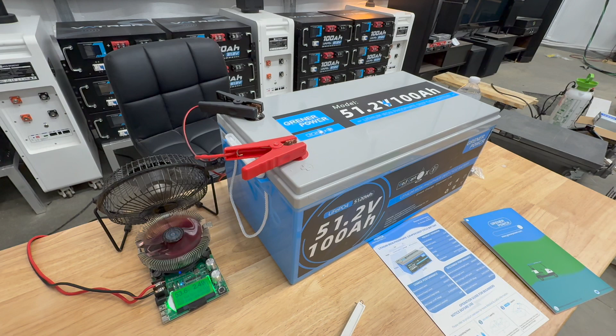Once you take a battery like this and put it into use, since it's 48 volt, use a T-class fuse - highly recommended, so it's got the interrupt capacity to extinguish the arc. You have to remember this BMS can put out 600 watts, or 600 amps peak, and 600 amps can melt quite a few wires. So make sure you have a thick enough gauge wire to handle the load you're going to put on it, and fuse it for that wire thickness.